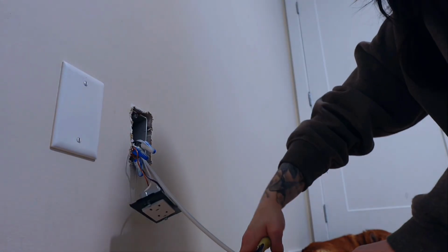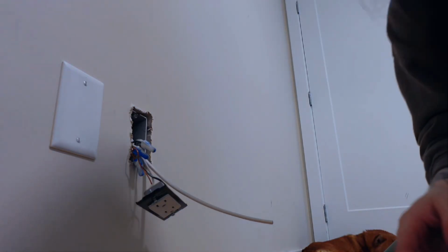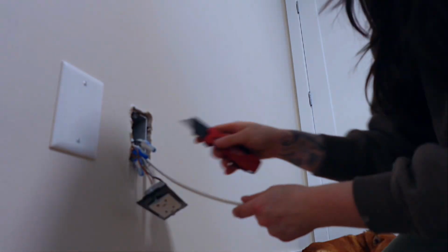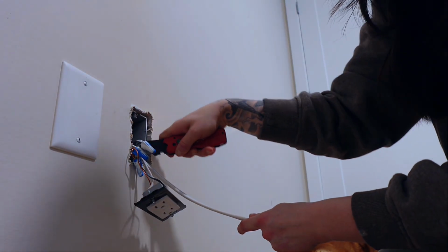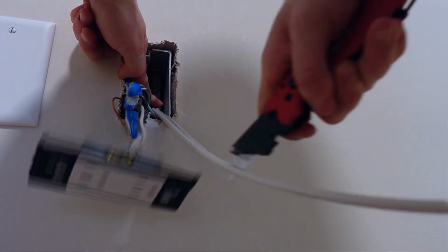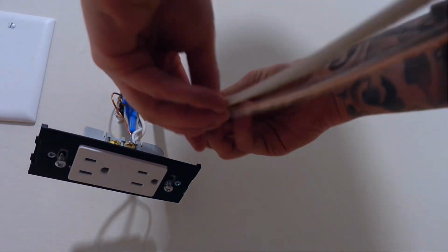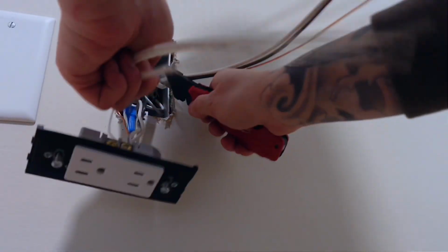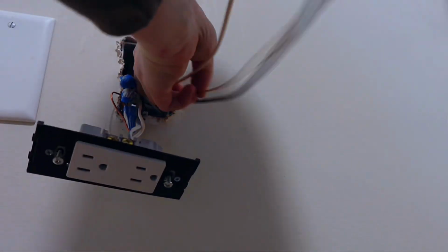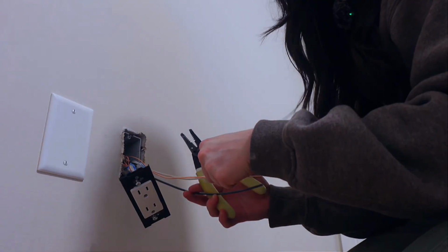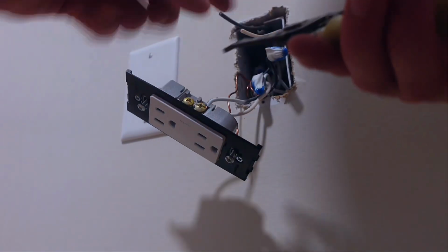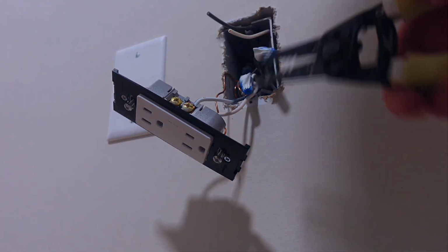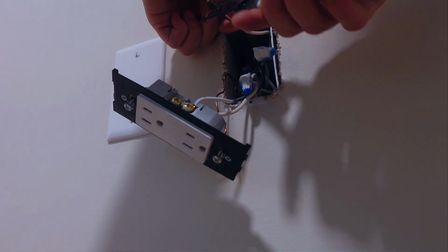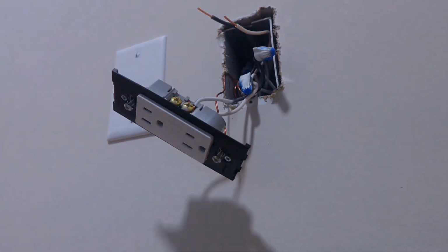There we go. Next, I'm gonna cut the wire to length. And we're gonna grab our knife and strip this wire, score it down the center. Now that our wire is stripped, we're gonna splice in our bond, our neutral, and our hot wire into the Marrettes. To strip the wire, I take the 14 gauge solid hole, and you're just gonna place it around there, give her a little wiggle, and it will nicely strip the wire for you, or score the wire for you.